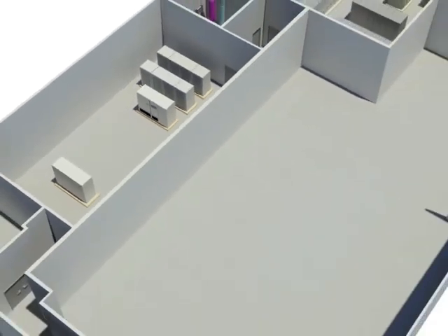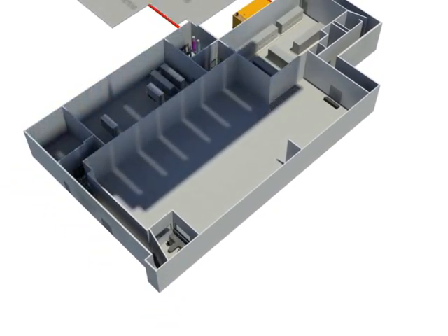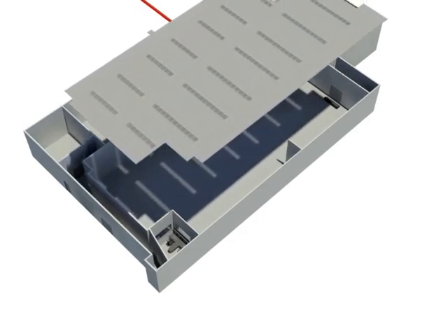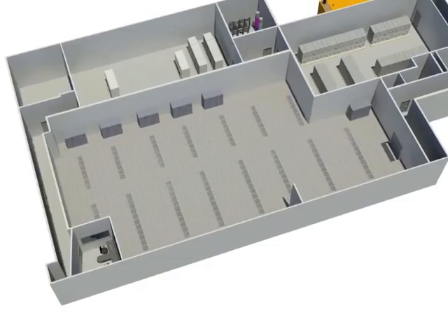The inside of the data center is intricately engineered to provide an optimal operating temperature at all times. 5,100 square feet of the total 12,074 square feet facility are engineered with 12-inch raised floors to circulate cool, temperature-controlled air into server rooms through floor-level ventilation systems. 13 redundant high-capacity computer room air conditioner units with 177 tons of cooling and 9 20-ton Liebert Deluxe System 3 air handlers positioned throughout the facility pump chilled air into the data room and keep hardware at optimum operating temperatures of 68 to 72 degrees Fahrenheit.